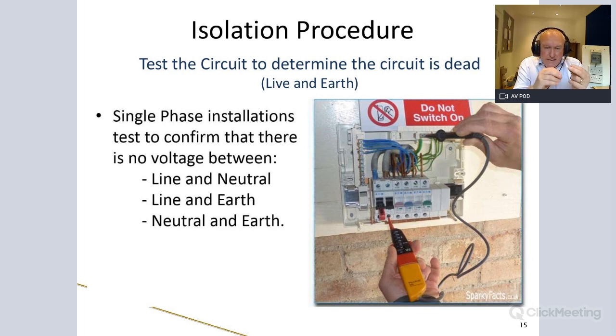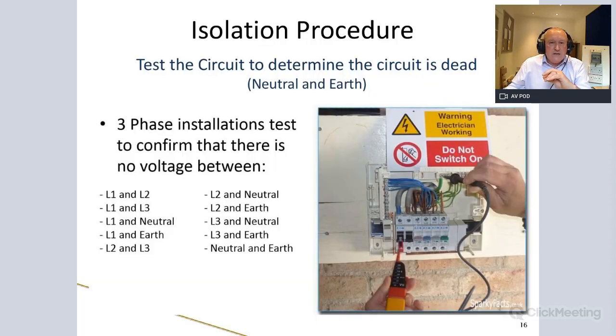In reality, it doesn't matter which way you go around. You could start with neutral and earth, or earth and live, and finish with neutral. It's not critical, and different books and teachers teach different ways. I'll show you my way at the end, but that doesn't mean it's the only right way. So long as you test all 3 points, it doesn't matter what order you do it in. But I'll show you my version, since I think there's a good reason for it, and I'll explain that at the end of the session.